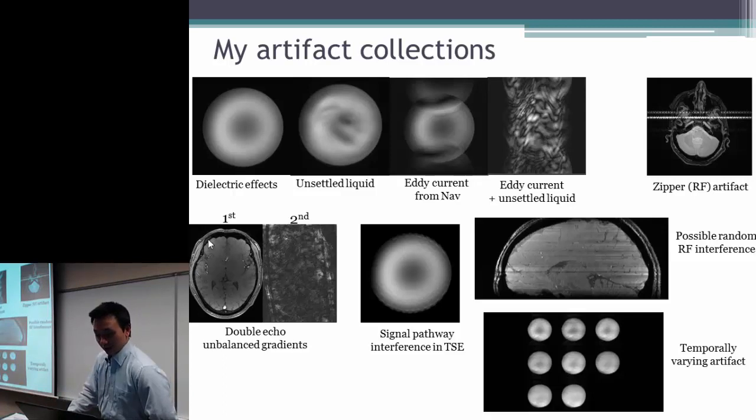It is well reconstructed, but for the second echo, all those signals are just destroyed and dispersed. So basically, there's no usable information. This is caused by the unbalanced gradients that I used before the second echo. When I saw this image and I know my sequence, I can immediately tell the problem, and then we solve the problem by adjusting the gradients accordingly.